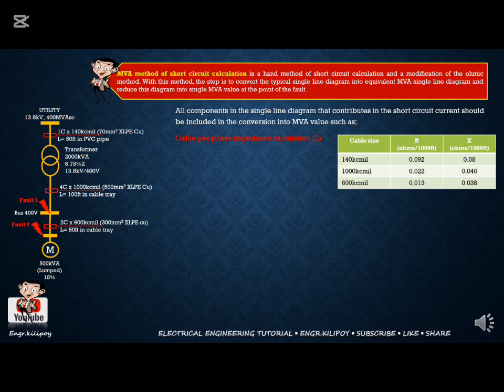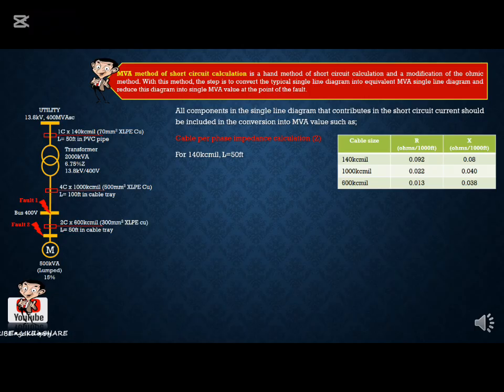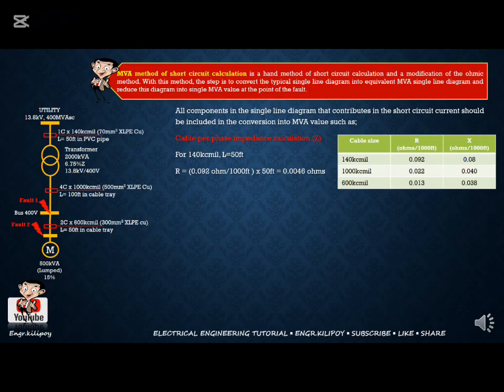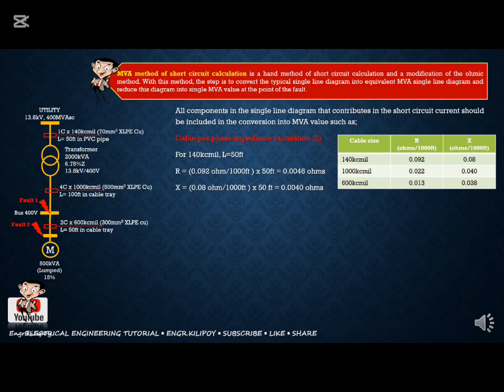Okay, so for the impedance calculation, kailangan mo yung data ng size ng cable and yung length, at the same time yung number of parallel conductors. For the R value, since this is per 1,000 feet, multiply natin siya ng length, makakakuha tayo ng 0.0046 ohms para sa resistance value ng 140 kcmil na cable. Same as in the reactance value, which is 0.0040 ohms.